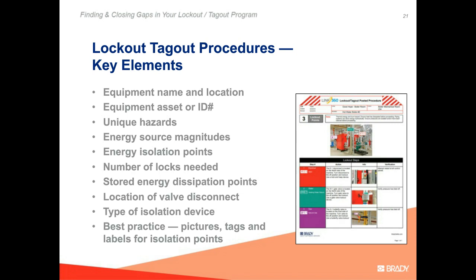The energy steps should go from the highest hazard to least hazard and include the magnitudes for each energy source. So for electric, that's including the voltage of 480 volts or 240, or for any of your pressurized pneumatic air coming in, you need 100 PSI or whatever PSI you have at your facility.